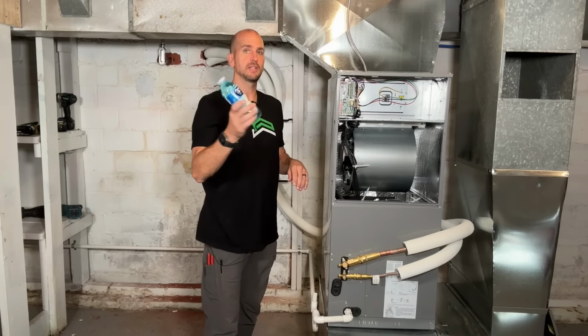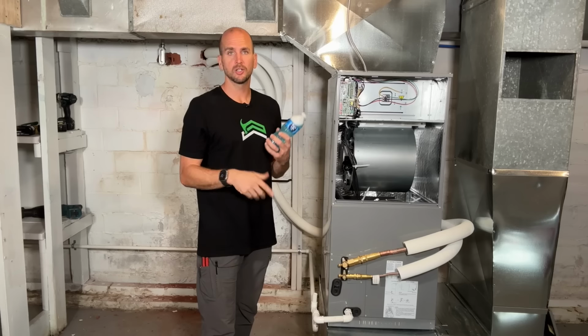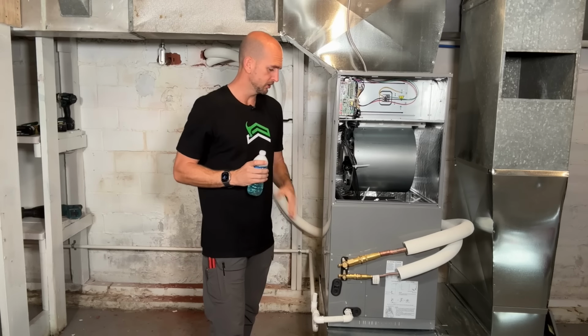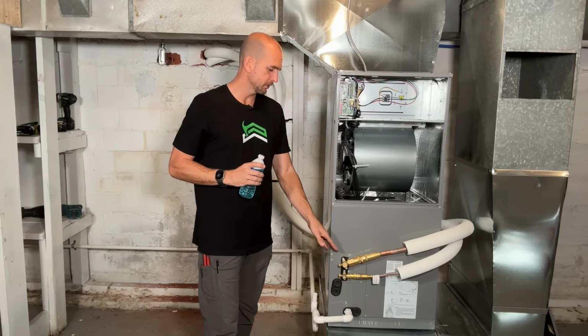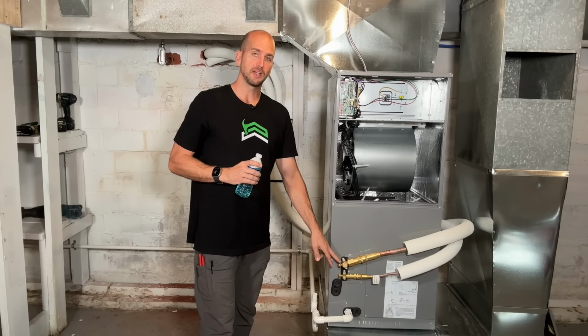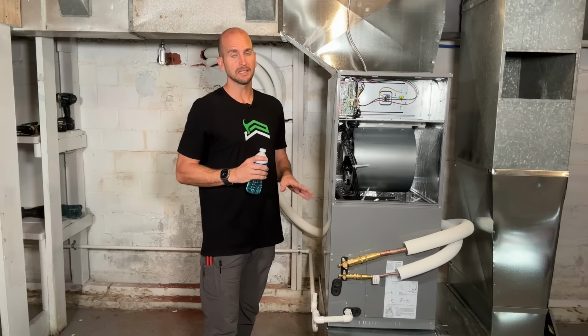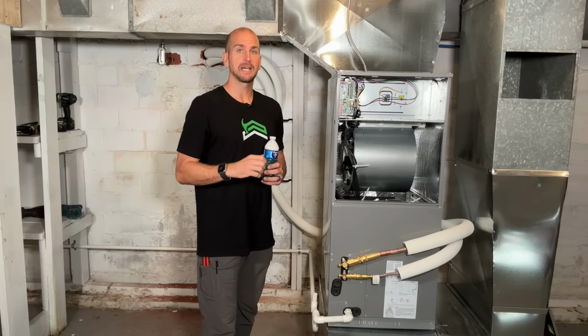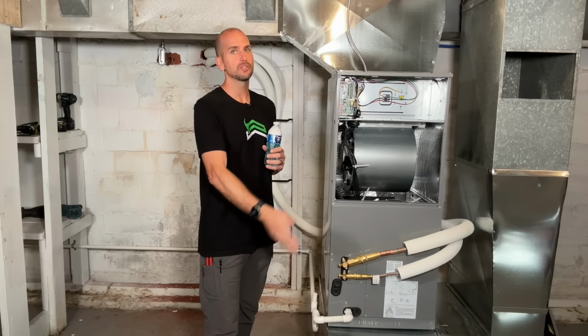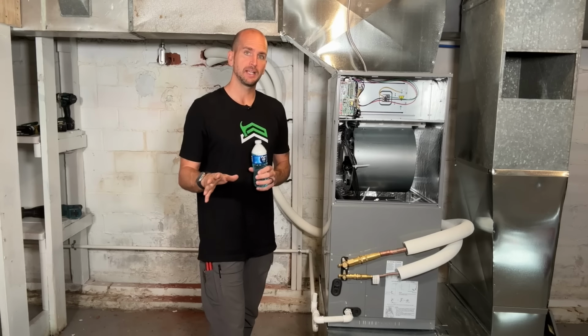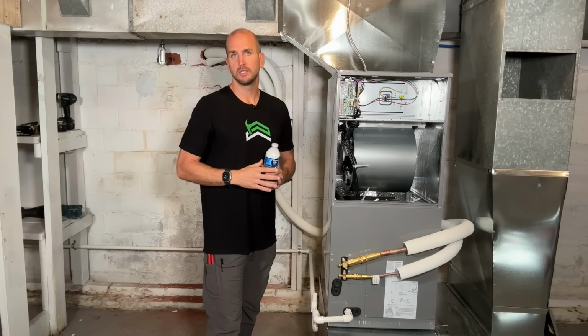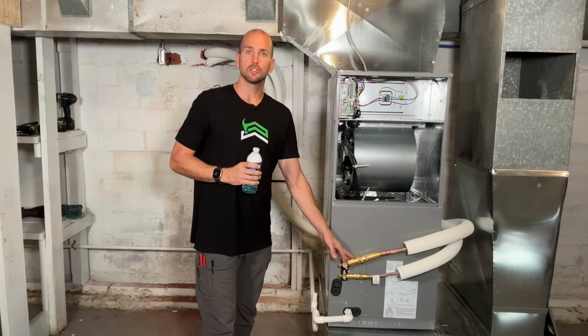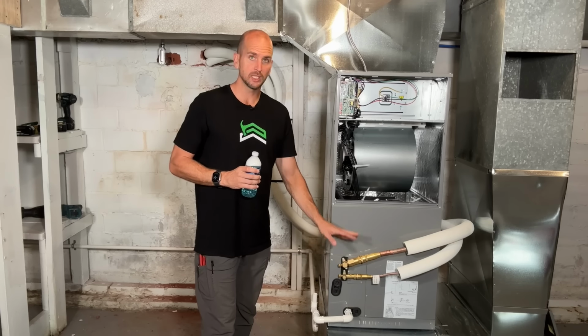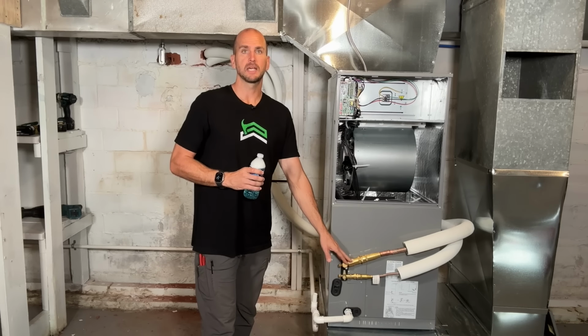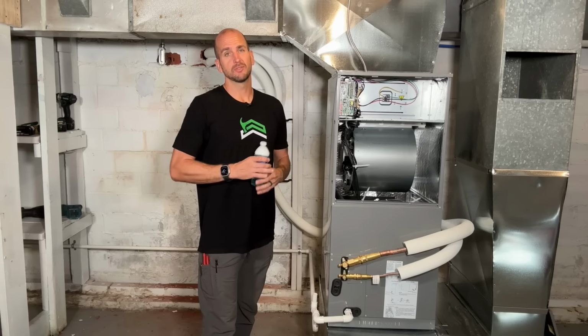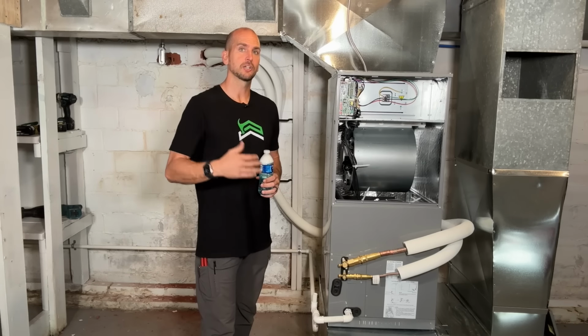So really all I have is some dish soap and water. I'm gonna pour that on, maybe you have a spray bottle. I'm gonna pour it on these connections that we made, and then I'm also gonna open up these valves. So I'm gonna look for any bubbles to indicate any leaks. If we do have a leak, we want to get that stopped as soon as possible, because once the refrigerant actually goes out of these lines, if that happens to you, now you would need to call in an HVAC tech. They need to pull in new refrigerant and pull that vacuum, which they can do. In the instructions, it tells them exactly what to do, but obviously that turns it from not a DIY project and you gotta kind of call in some help.